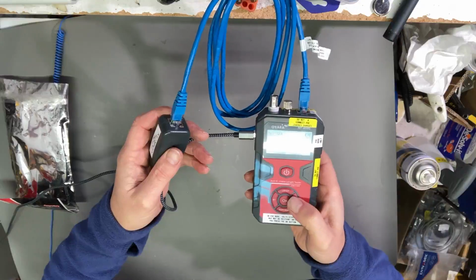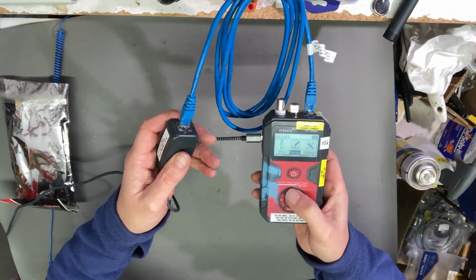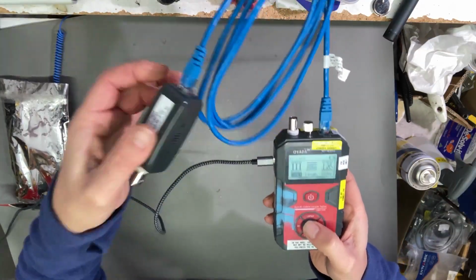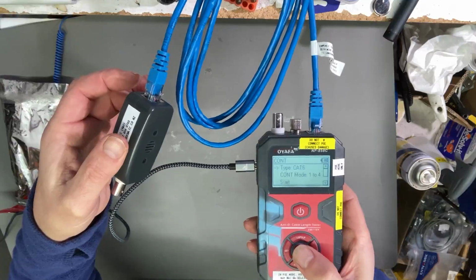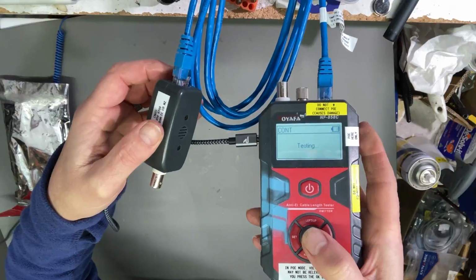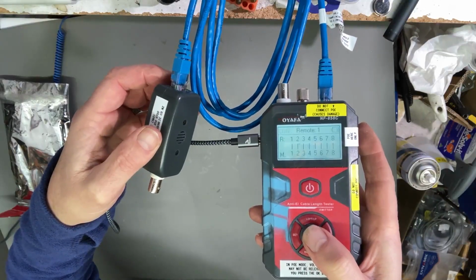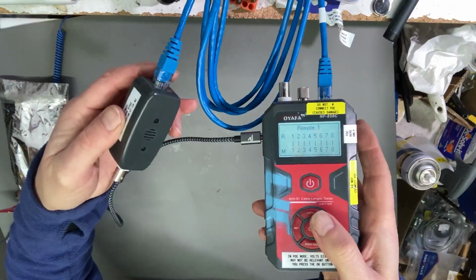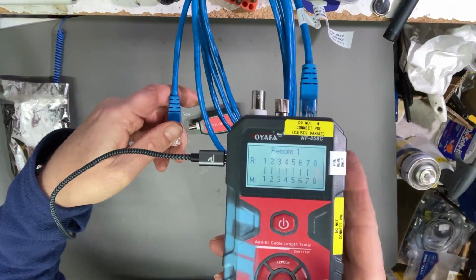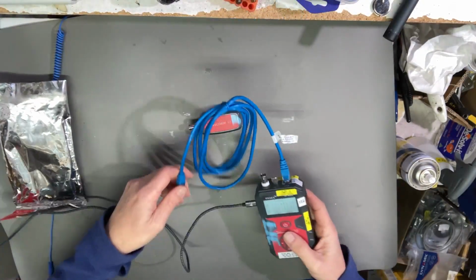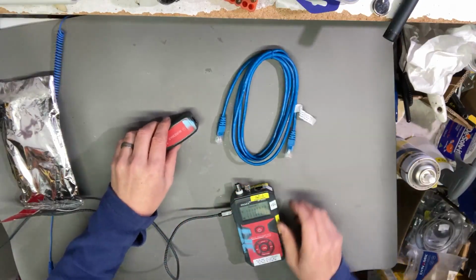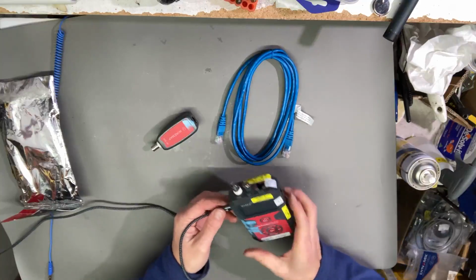Let's take this to the continuity test. So here we are, continuity. I've got the cable connected, the remote at this end, and if we go down to start, it's doing the test, and then the remote is beeping. I'll just disconnect the remote, and we can see that it's got a valid test result, continuity. Now the thing with this cable though is it's actually a bad cable. So why did it test okay with our continuity meter?